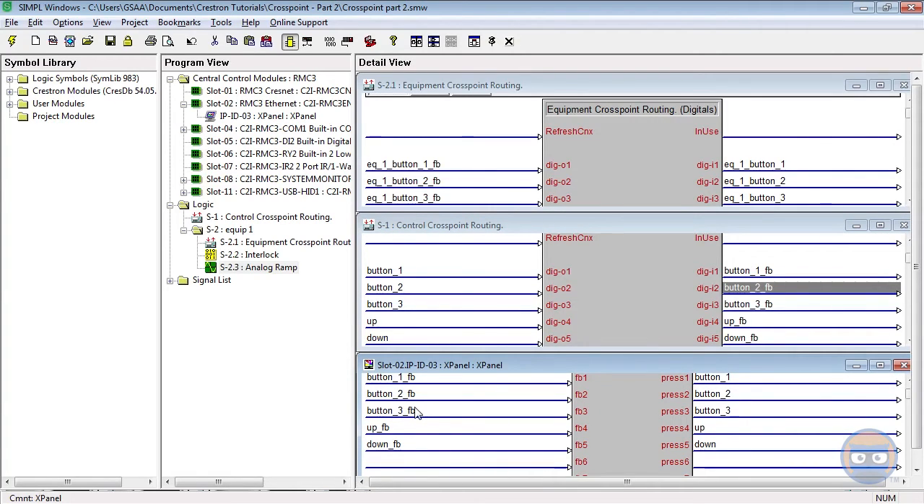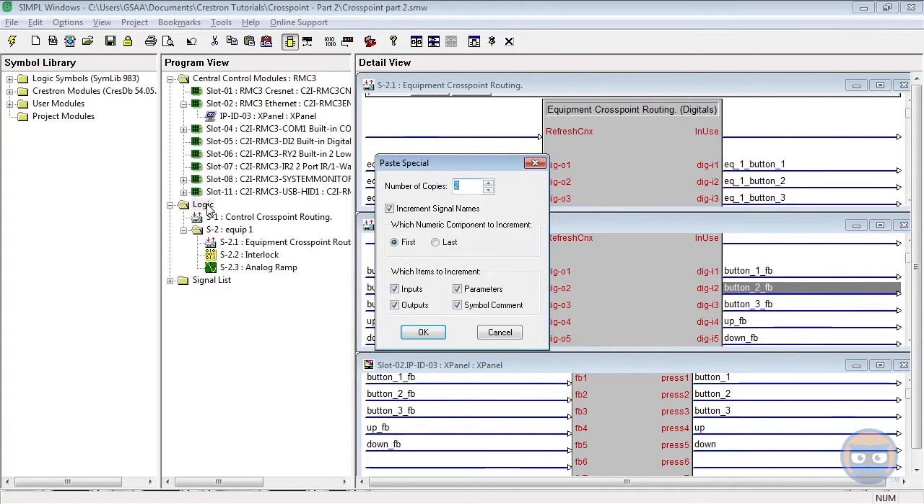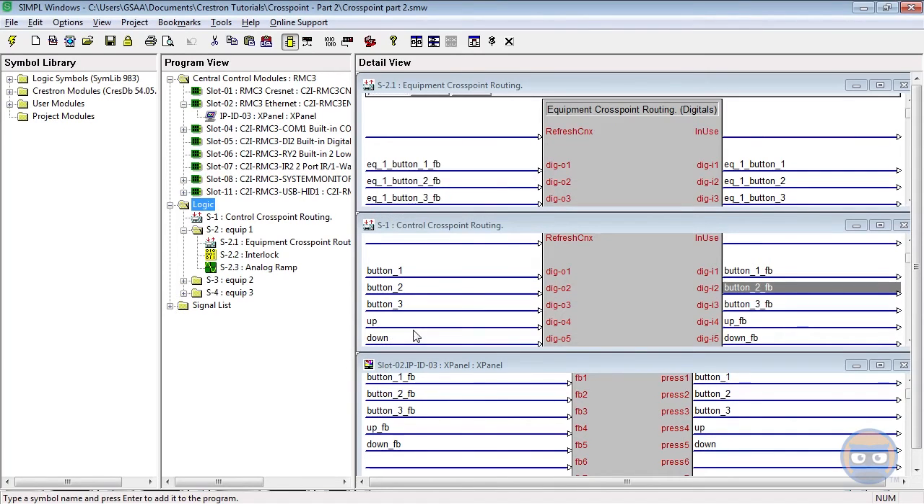In most cross point applications you'll usually have the same logic in a lot of different zones. So instead of writing that same logic over and over, let's use the special copy-paste methods in SIMPL Windows. I'm just going to click the folder containing the logic we want to duplicate, hit Control+C, click the logic folder at the top, and press Control+Shift+V. Here we can specify which parts we want to change. What this is going to do is take any numbers that paste special senses in the signals and increment them — kind of like hitting F4 but for a whole group of symbols. We're going to leave this at two copies of the equipment logic and hit OK.